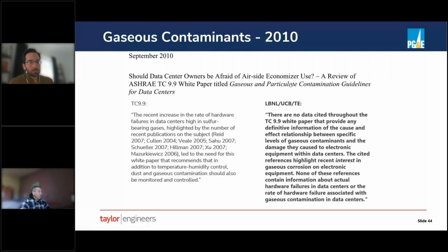ASHRAE TC9.9 came out with a white paper, I guess now it's 15 years ago, that really sounded the alarm. The white paper said the recent increases in the rate of hardware failures in data centers led to the need for this white paper, which recommends that, in addition to temperature and humidity control, dust and gaseous contamination also be monitored and controlled.